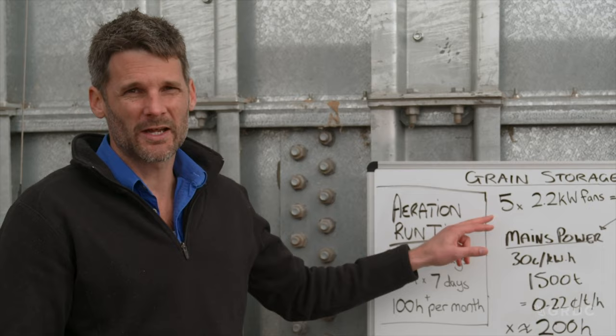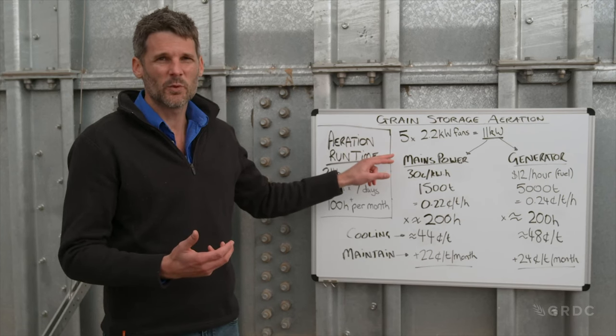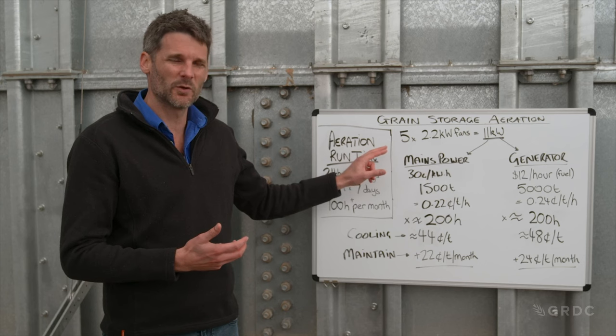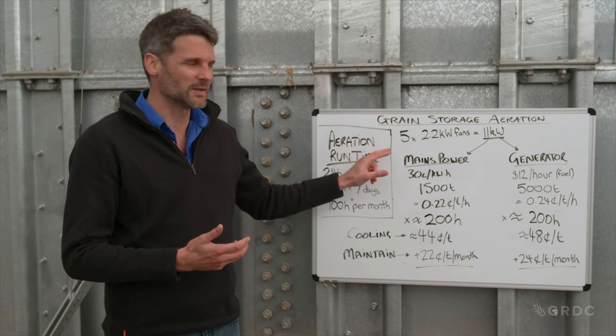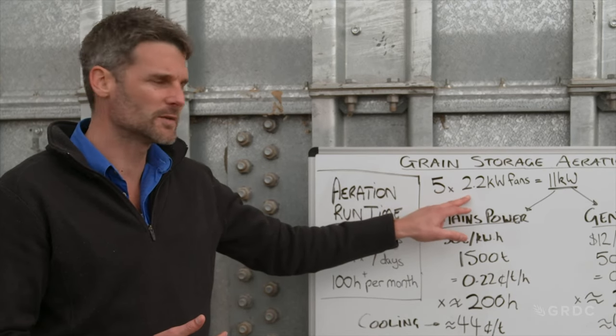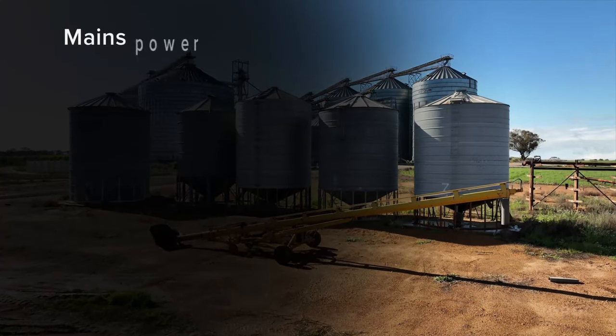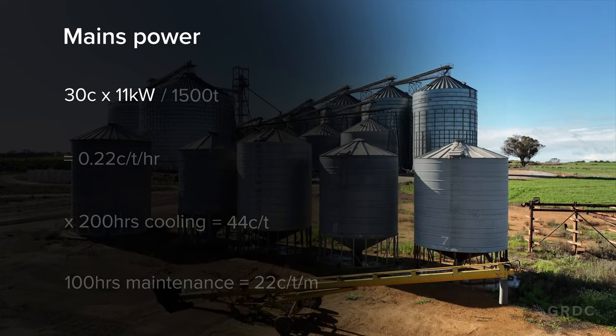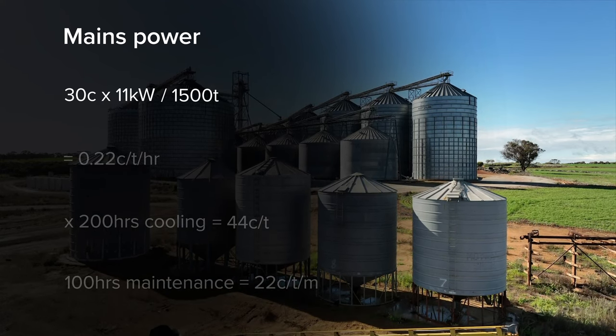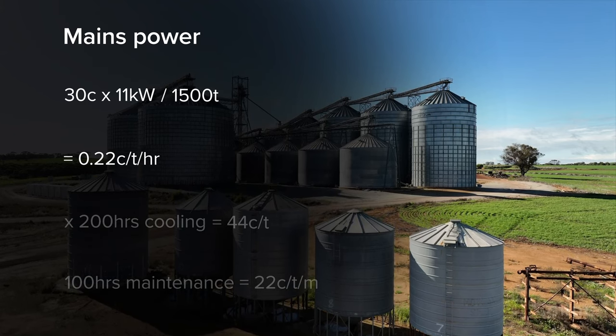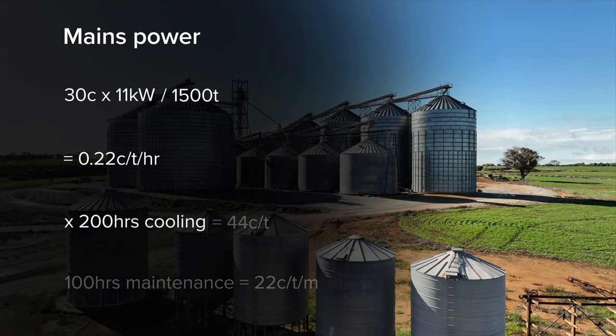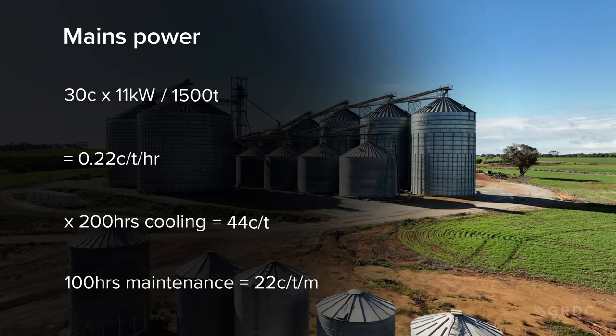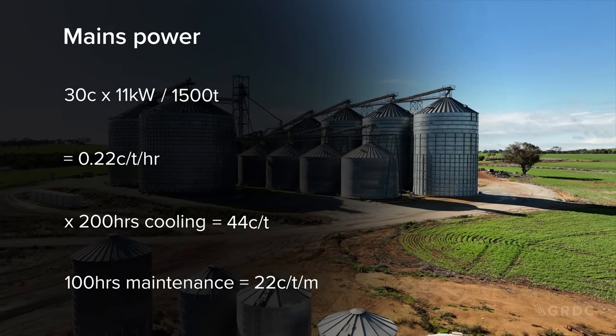What we've got here is an example of how to calculate the cost of running aeration cooling fans. The important thing is to use your own numbers of power cost for your own situation. We haven't considered the setup cost of a generator or mains power — that's something that's going to be site specific. In this example, we've got five fans of 2.2 kilowatts totaling 11 kilowatts. Using a mains power cost of 30 cents per kilowatt hour, multiplied by 11 kilowatts, divided by 1500 tonne in that silo, we've got about 0.22 cents per tonne per hour. Multiply that by 200 hours to cool the grain down, and our cost is about 44 cents a tonne. For every month after that for maintenance, we're looking at about 22 cents per tonne.